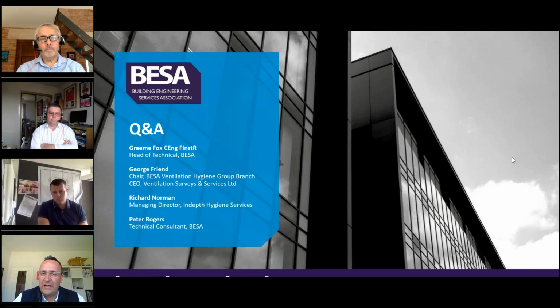George, anything to add on that? Yeah, that's true. You should have 2. It's possible to do a test and maintenance activity with 1, but that doesn't negate the fact that you should have 2, because the reason we ask for 2 is, should a damper fail or get wedged, you may need someone to go the other side of the fire compartment to assist in resetting it.